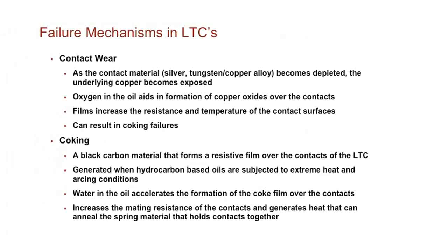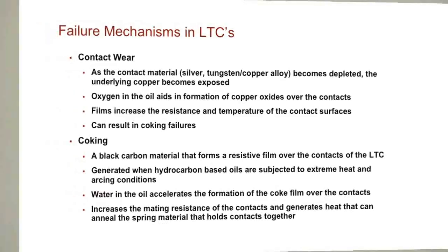One of the main concerns for LTC is the contact wear. Basically, that's your current carrying component inside the LTC. When you have contact wear, basically it's when the unit's switching from one tap to another. You have electrical contacts, you have arcing contacts. Most of them are copper, some of them are silver inlaid material today to help them extend the life of the contacts. But when those contacts are sliding together, they're making friction, so you're going to have those issues as well.